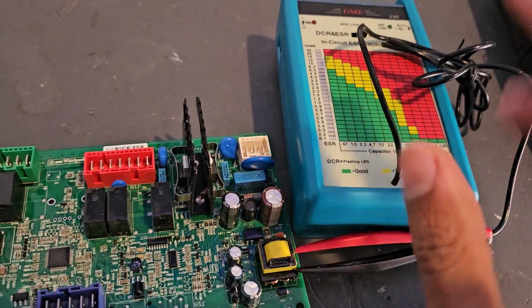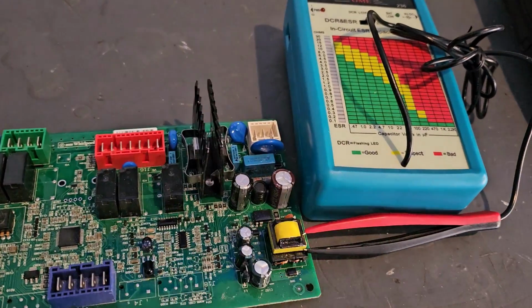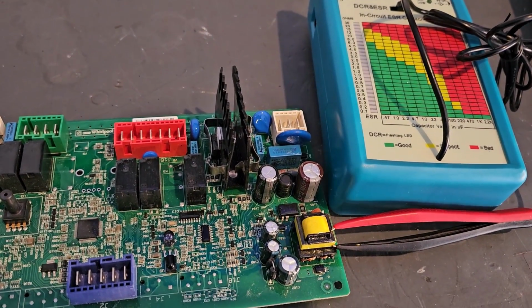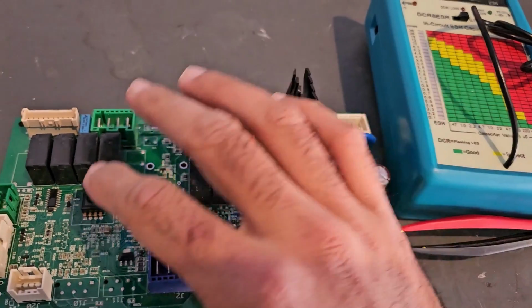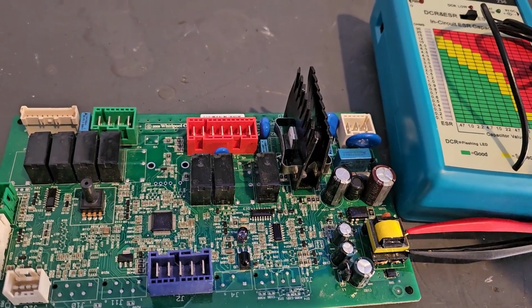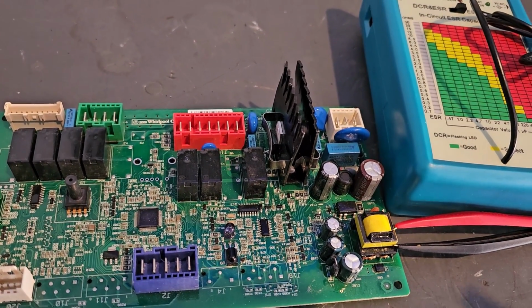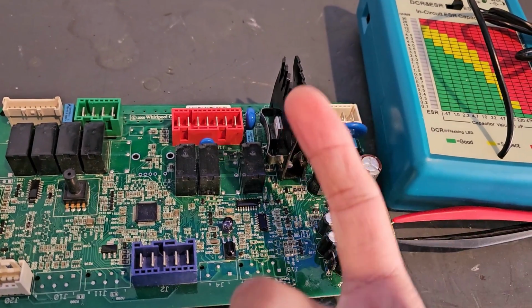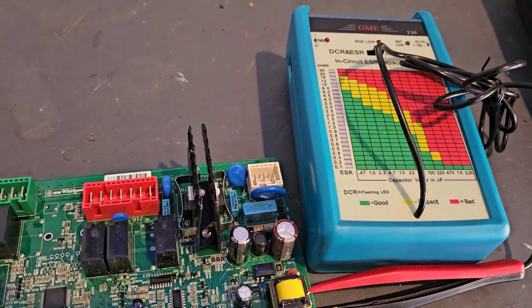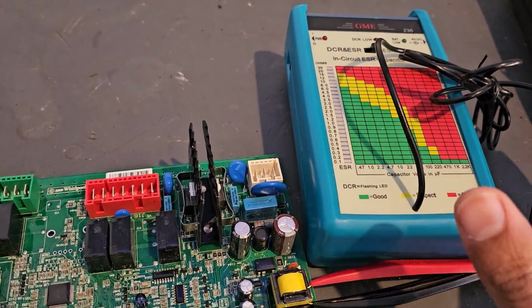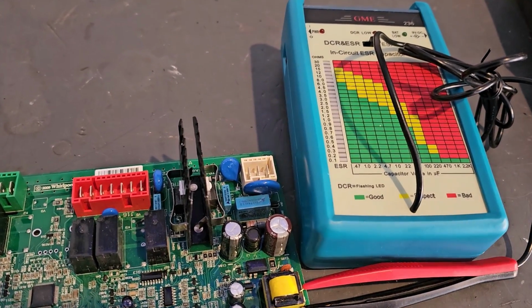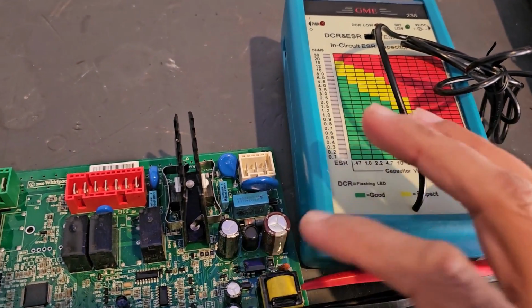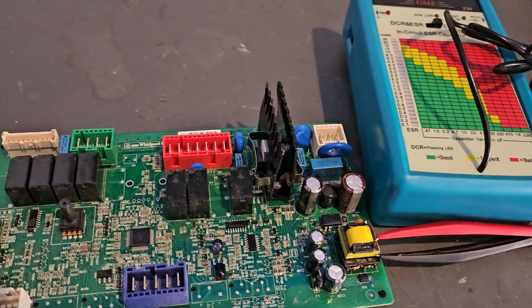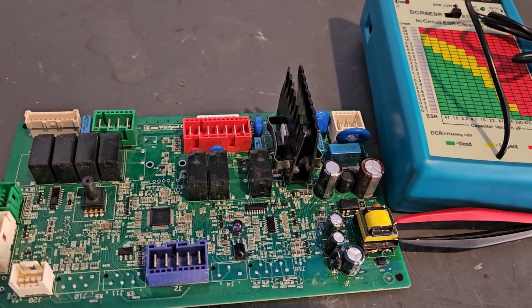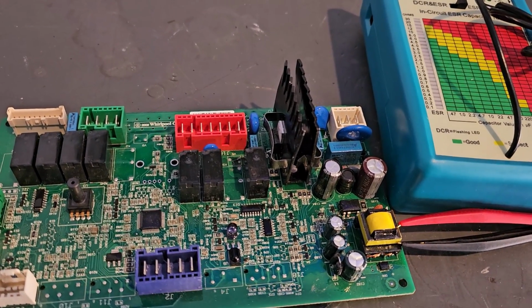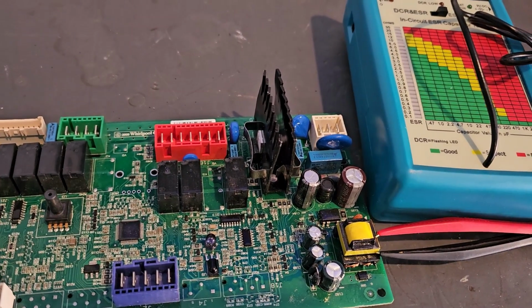So that's two things I do immediately after pulling out a control board, or if I suspect a control board issue. And obviously, I check the input and output voltages. But after that, if I suspect that it is a control board issue, I'll check for physical damage. Then I'll pull out my ESR meter and I'll check the ESR or the resistance on these capacitors. It's really easy to go through an entire control board full of capacitors and check their resistance within 5 or 10 minutes.